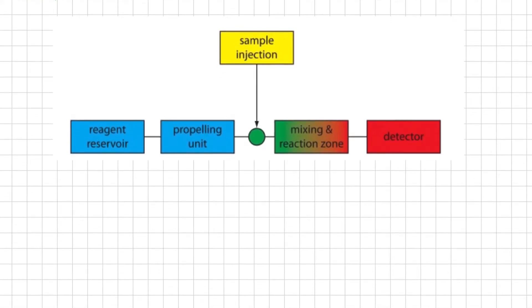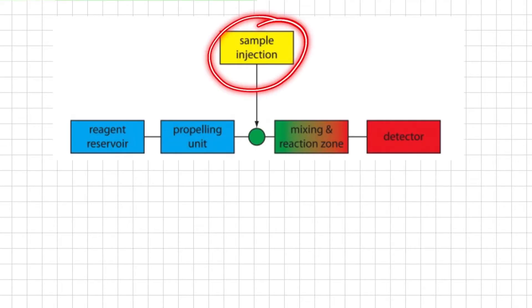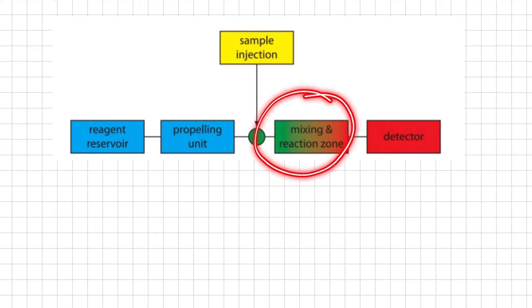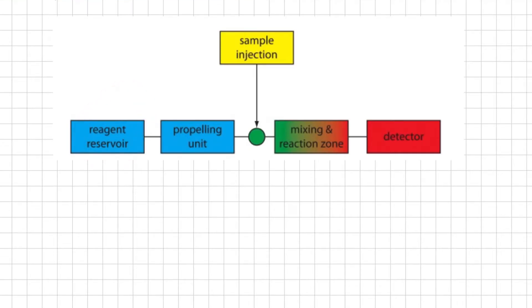A schematic diagram of the basic concepts of flow injection analysis is shown in this figure. The reagent serving as the carrier is stored in a reagent reservoir, and a propelling unit maintains a constant flow of the carrier through a system of tubing that comprises the transport system. We inject our sample directly into the flowing carrier stream, where it travels to one or more mixing or reacting zones before reaching the detector or flow cell. This is the simplest design for the flow injection analyzer, consisting of a single channel with one reagent reservoir. Multiple channel instruments that merge separate channels, each introducing a new reagent into the carrier stream, are also possible.